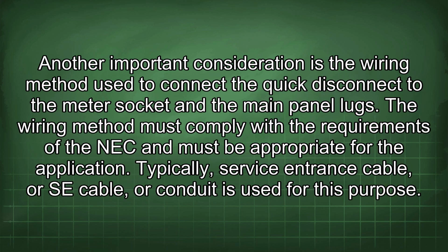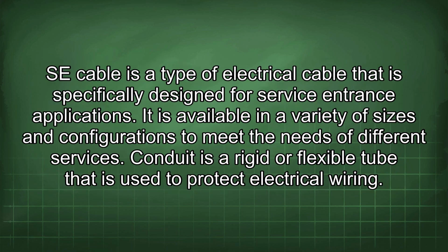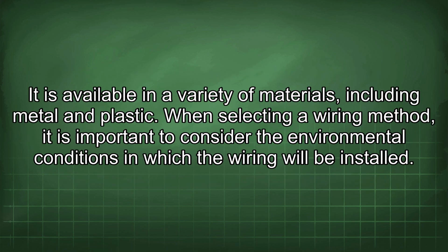Another important consideration is the wiring method used to connect the quick disconnect to the meter socket and the main panel lugs. The wiring method must comply with the requirements of the NEC and must be appropriate for the application. Typically, service entrance cable, or SE cable, or conduit is used for this purpose. SE cable is a type of electrical cable that is specifically designed for service entrance applications. It is available in a variety of sizes and configurations to meet the needs of different services. Conduit is a rigid or flexible tube that is used to protect electrical wiring. It is available in a variety of materials, including metal and plastic.